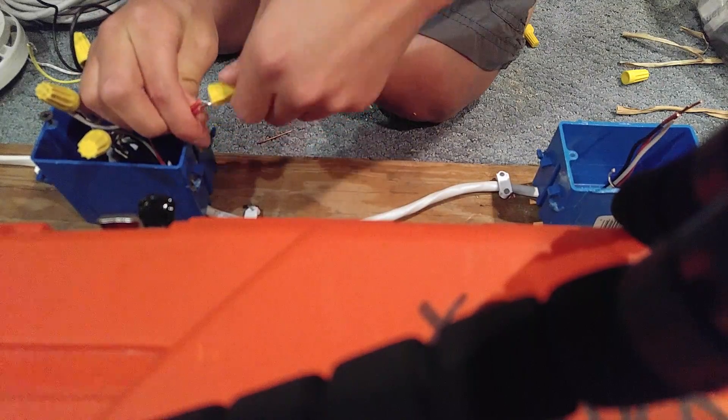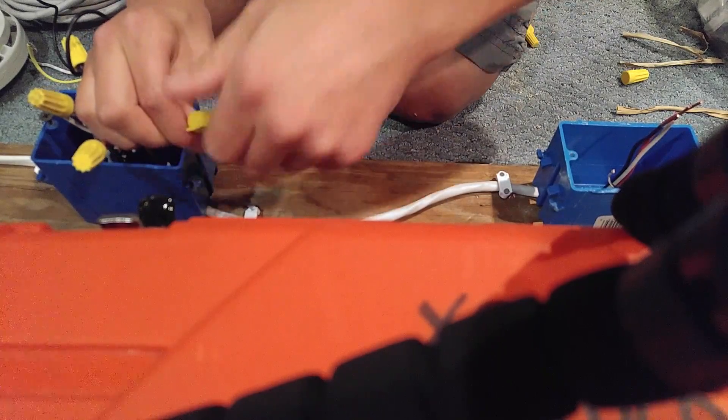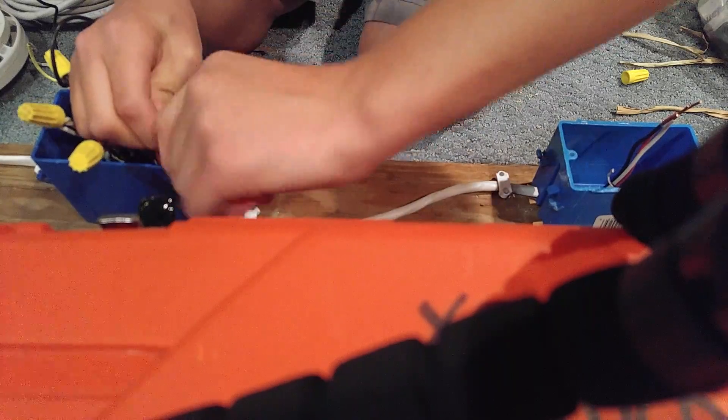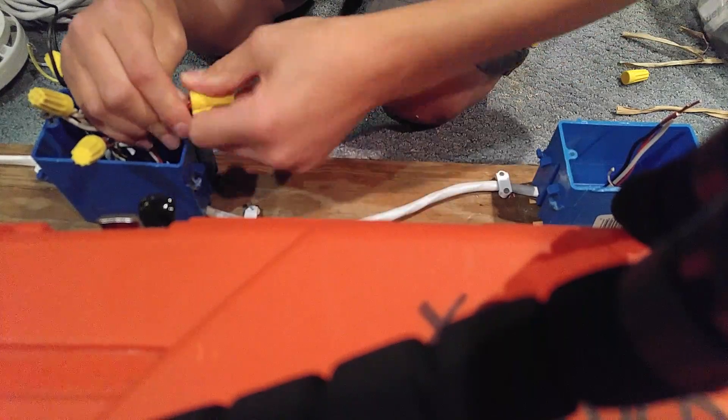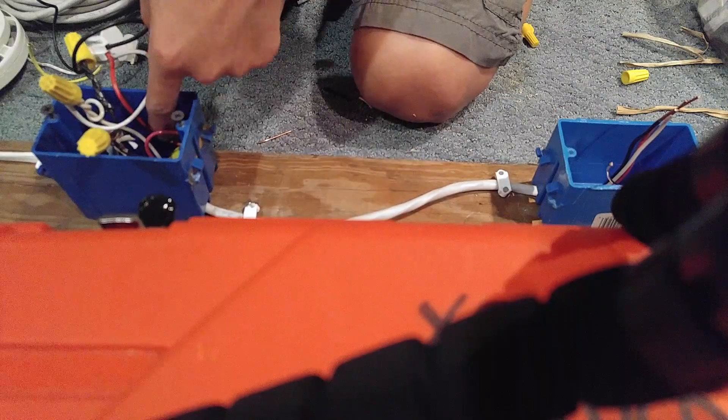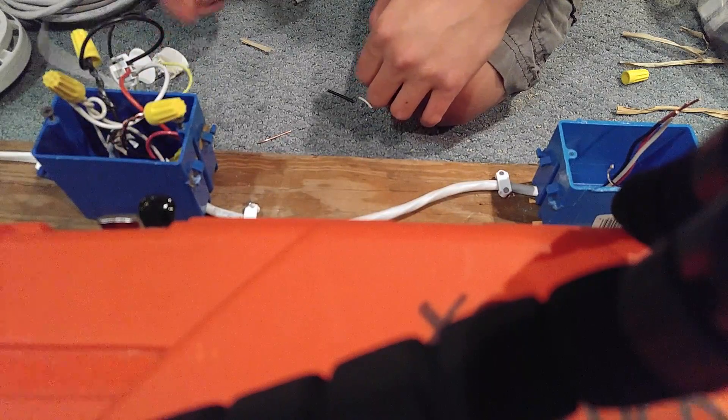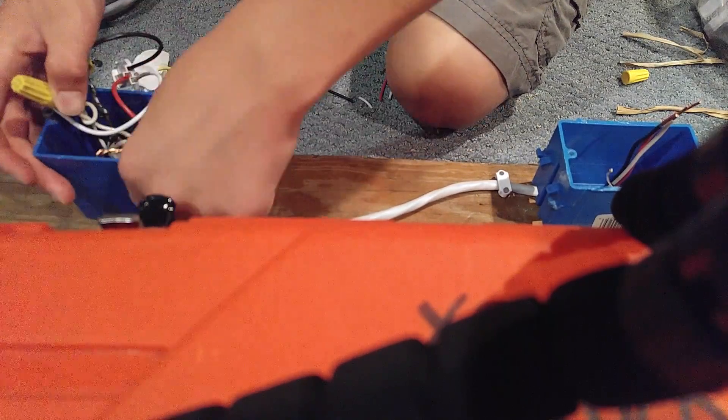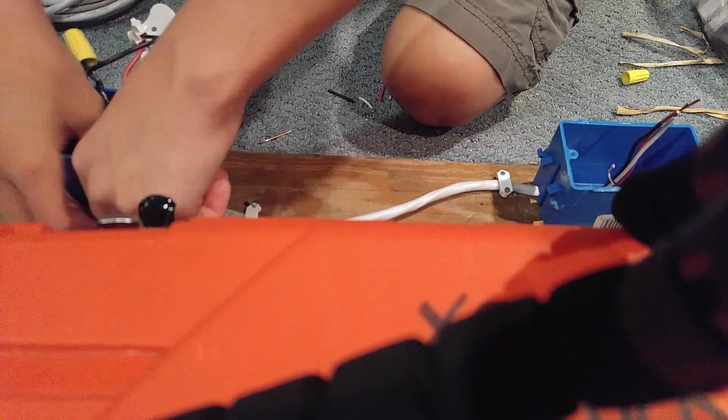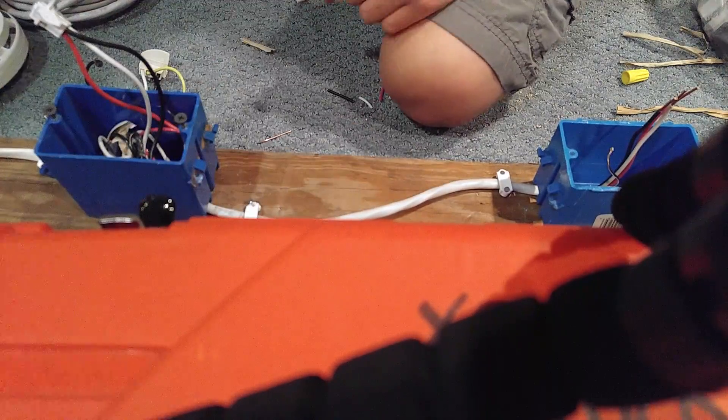Now you don't need so much of that wire, so I'm just going to cut it, trim it. Put the wire together, put a nut on. This is a single wire, I'm going to use a smaller nut to make it a little easier for me. You can also use, by the way folks, Wago or Ideal wire connectors. I've heard they're really easy to use and I'm not against that. Just push and fold your wires into the box. Now I think I said this before, but smoke detectors do not use grounds. So for safety, just put your ground in the box. They're going to look for that when they inspect your home. Keep it there for safety. Don't cut it, just keep it there, twist it together and keep it there.